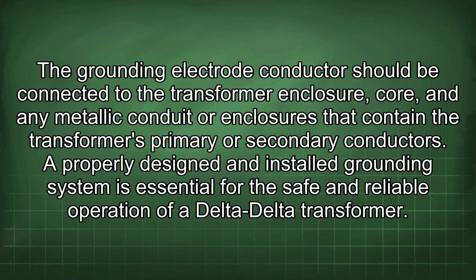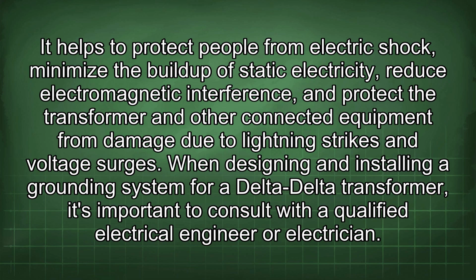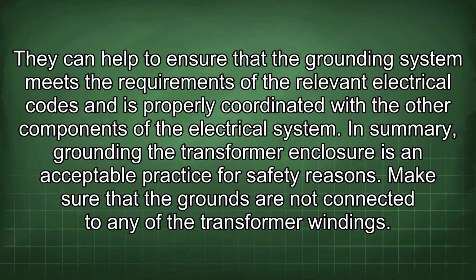A properly designed and installed grounding system is essential for the safe and reliable operation of a delta-delta transformer. It helps to protect people from electric shock, minimize the buildup of static electricity, reduce electromagnetic interference, and protect the transformer and other connected equipment from damage due to lightning strikes and voltage surges. When designing and installing a grounding system for a delta-delta transformer, it's important to consult with a qualified electrical engineer or electrician. They can help to ensure that the grounding system meets the requirements of the relevant electrical codes and is properly coordinated with the other components of the electrical system.